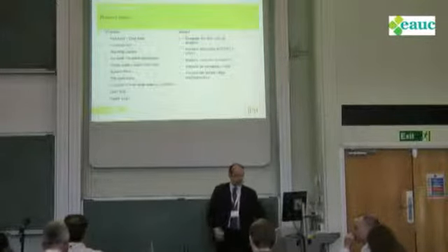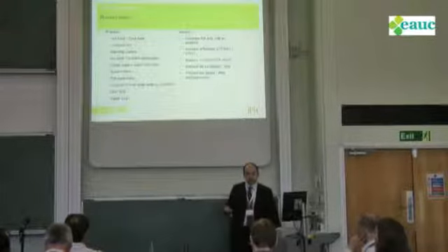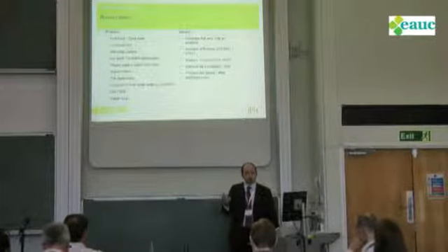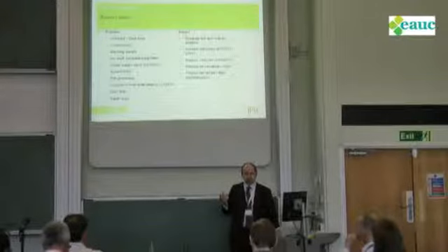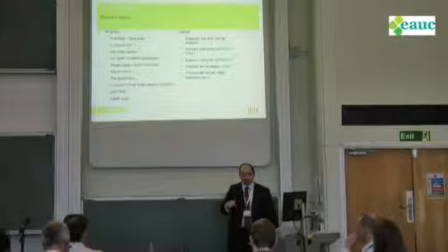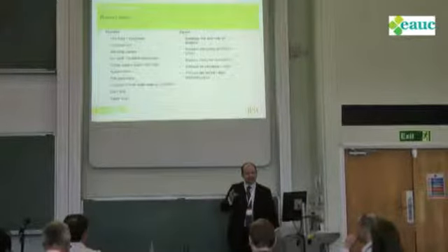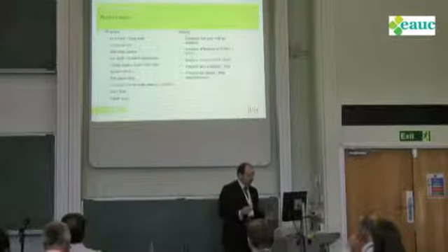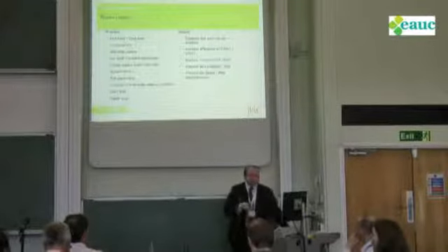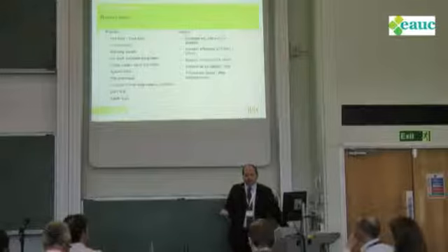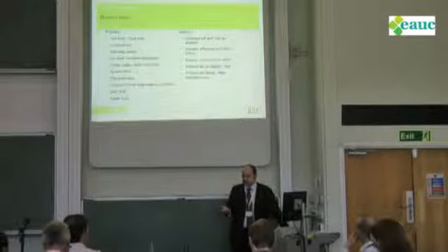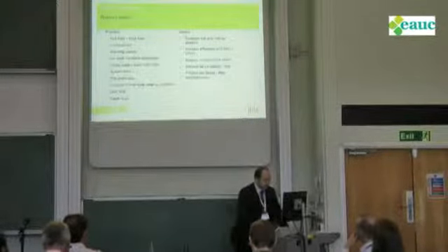Yeah, you're right, James. It's very counterintuitive. One of the other things, if you're having problems cooling your data centre because it's a very high temperature, turn your set point up, not down. People make the mistake of thinking, I've got to run it colder, I've got to run it colder. Actually, that's less effective. By running it hotter, you're actually much more effective at cooling. It's weird, but there you go. That's what the best practices do. They give you these ideas that you probably might not have discovered on your own. So that's why it's so great to look at.